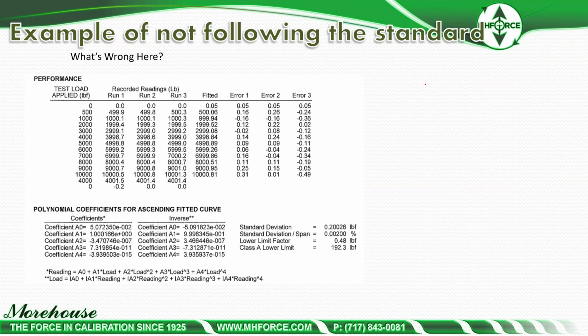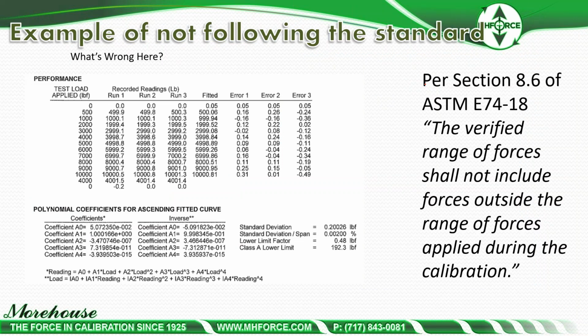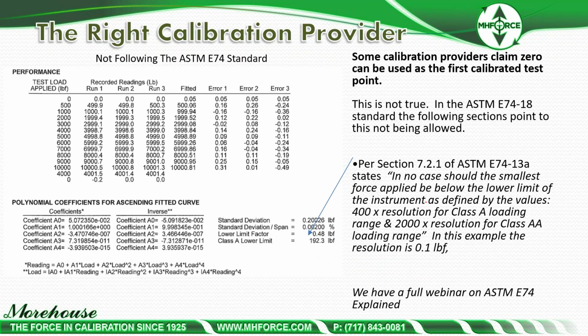Here's an example of not following the right standards. Here's an E74 calibration report. We see this all the time. It's basically saying the Class A lower limit right here is 192.3 pounds. It's not true because the first force point is 500. You're not allowed to use a non-tested force point. Section 8.6 says the verified range of forces shall not include forces outside the range of forces applied during calibration. If we continue to look at this, it's not true.